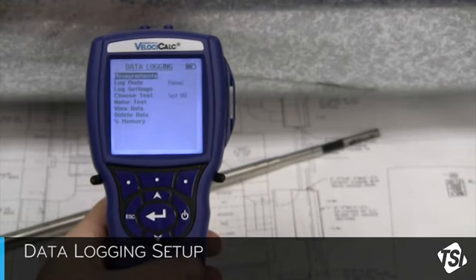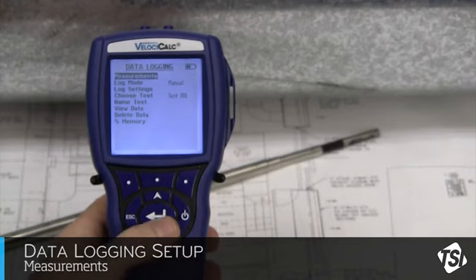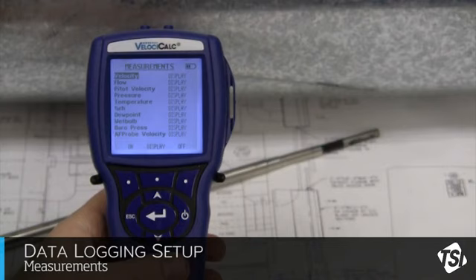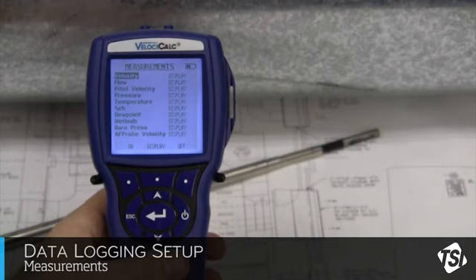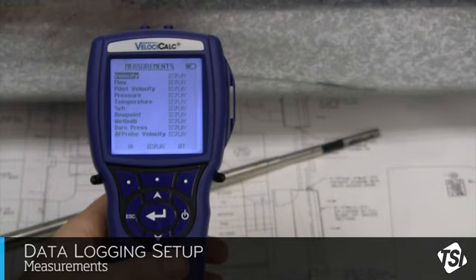First, we want to make sure the appropriate measurements are being logged. With measurements highlighted, click on the Enter button. If the unit is set to display, it means that if the measurement is displayed on the main screen, then that measurement will be logged. This is the default setting. Those measurements set to off will not be logged, and those set to on will be logged whether or not the measurement is displayed.